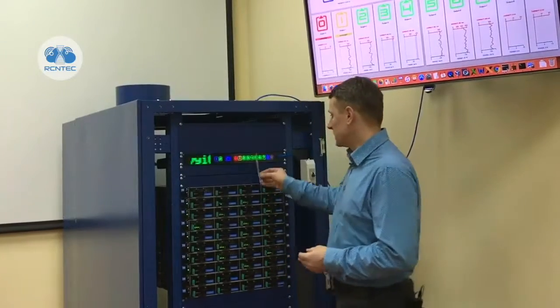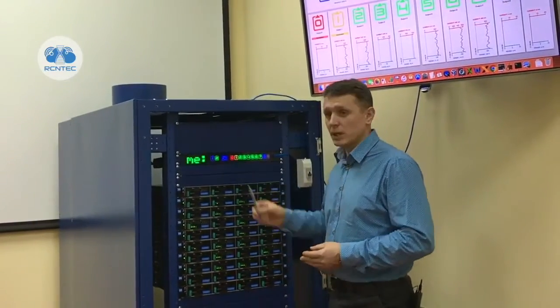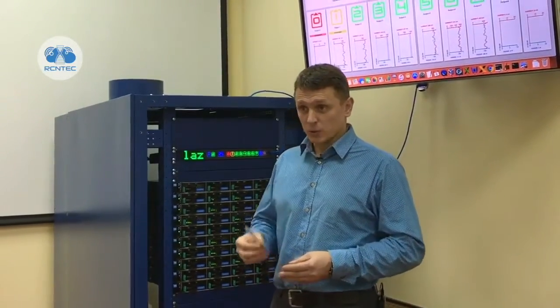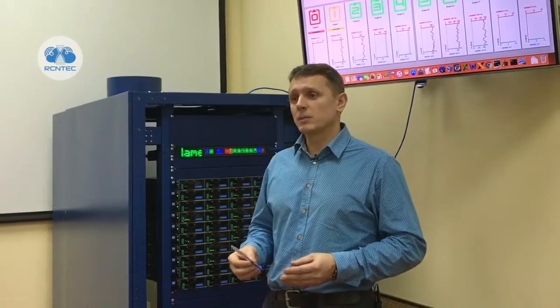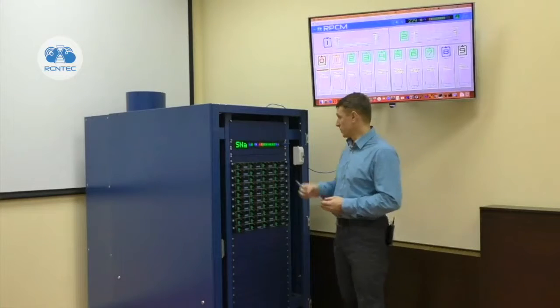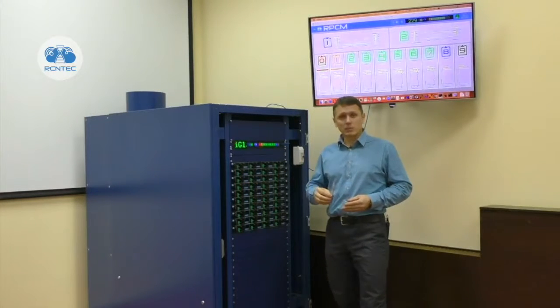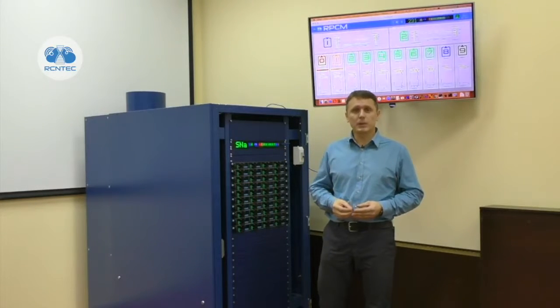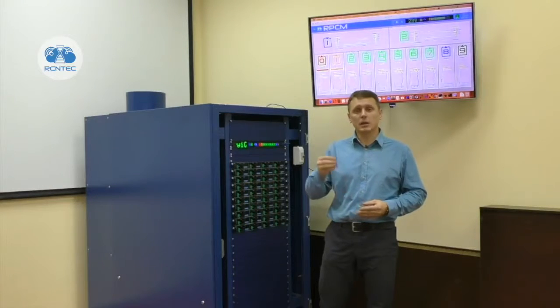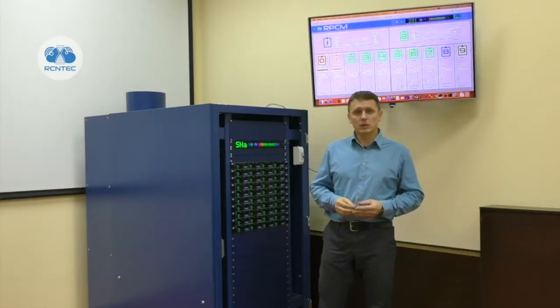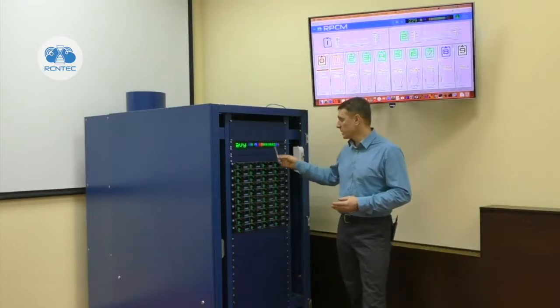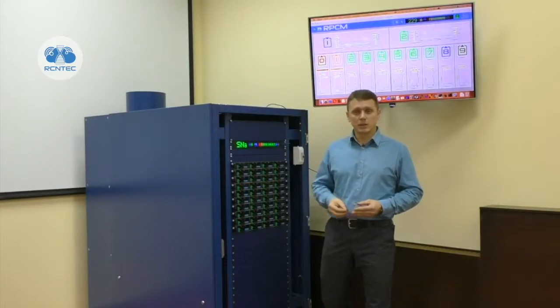Another very important function of RPCM is the short circuit protection implemented for each of 10 individual outlets. If a short circuit occurs, for example, in the power supply of one of the powered devices, RPCM automatically cuts off only the power going specifically to that device, thereby keeping the remaining consumers up and running, both the ones connected to the same RPCM and the others connected to the same bus bar.